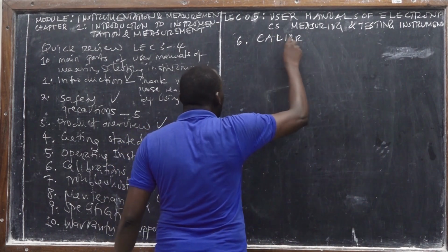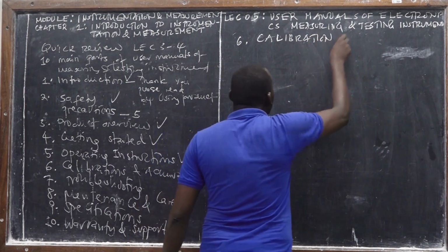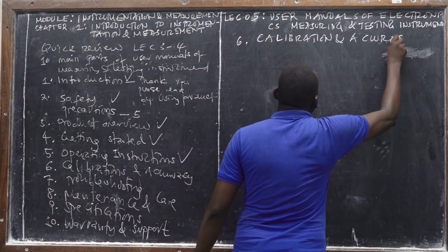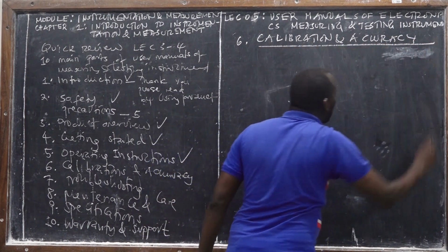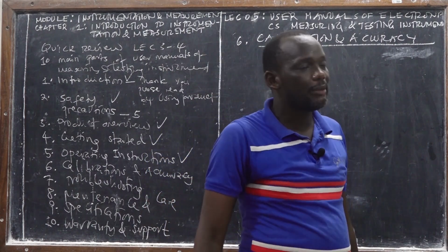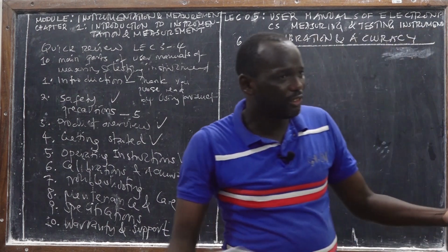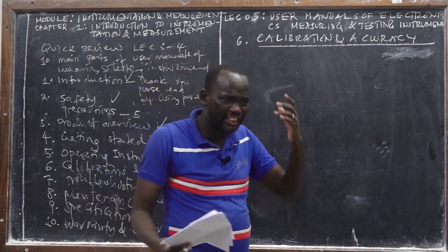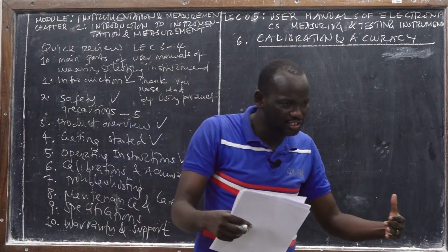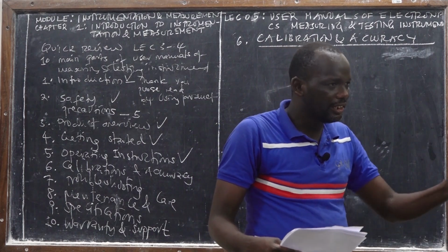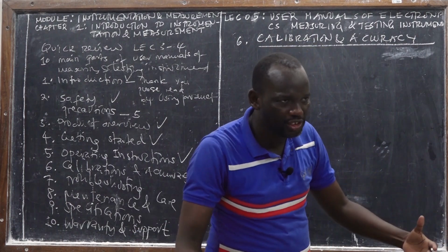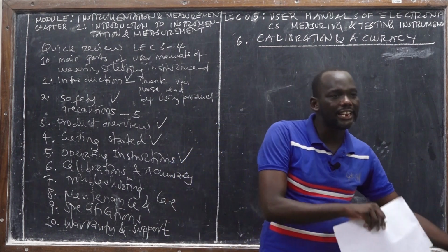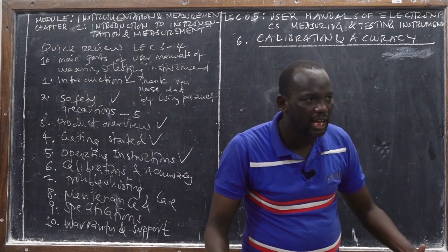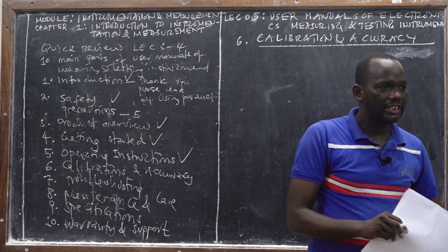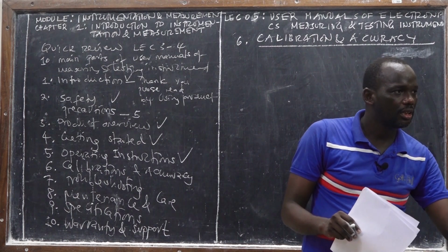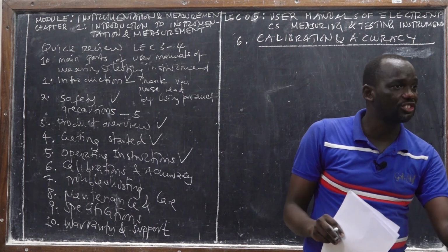Yes. So number 6 is a very important part, calibration and accuracy. This is a very important part in engineering. Class, say calibration and accuracy. Calibration and accuracy. What is the meaning of calibration? Why do we need to calibrate an instrument? Calibration is actually a process to set an instrument according to the standards. For instance, if measuring 1 ampere, then there is a reference standard that actually has to give a precise 1 ampere. So we set the instrument to follow the standards.